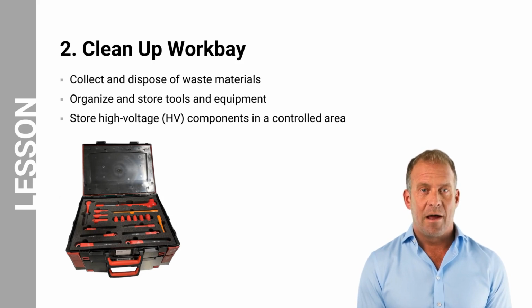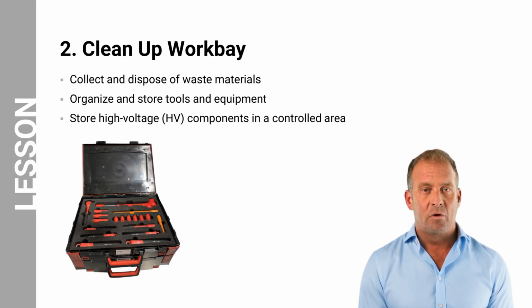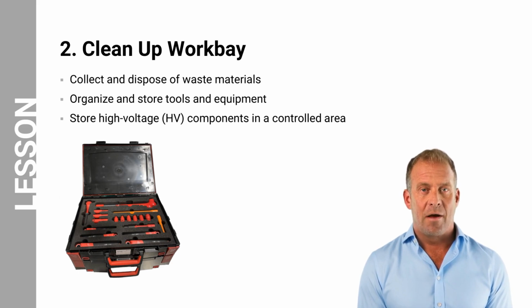Clearly label and identify any high-voltage components or panels removed during the maintenance or repair work. Use tags or labels that indicate their nature, purpose, and any relevant information. Use lockout devices or secure mechanisms to lock and secure the high-voltage components or panels in their designated storage areas if required. This prevents unauthorized access and ensures the safety of these sensitive components. Store high-voltage components or panels in a controlled environment that meets manufacturer recommendations. This may include considerations for temperature, humidity, and protection from contaminants.